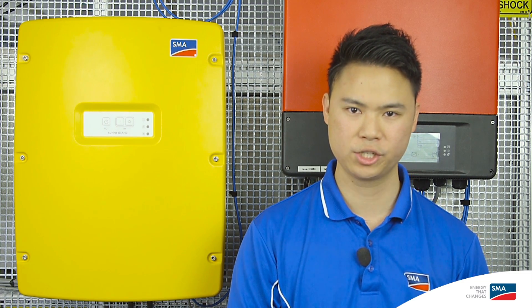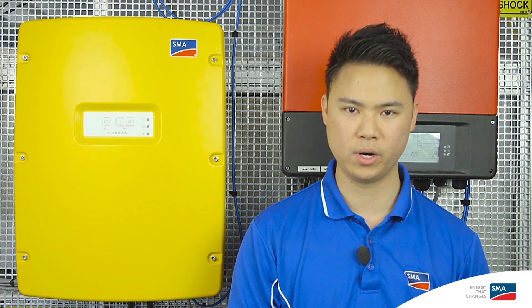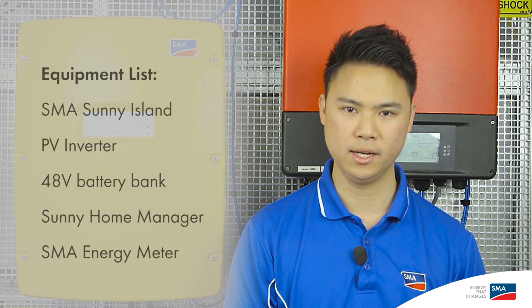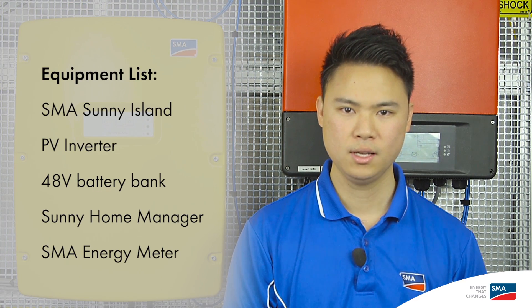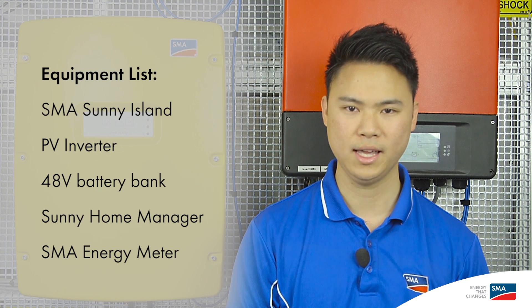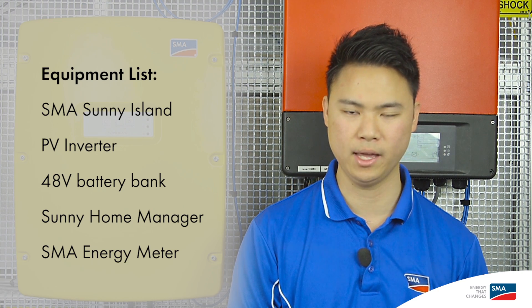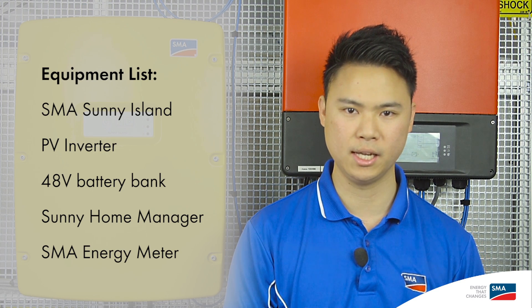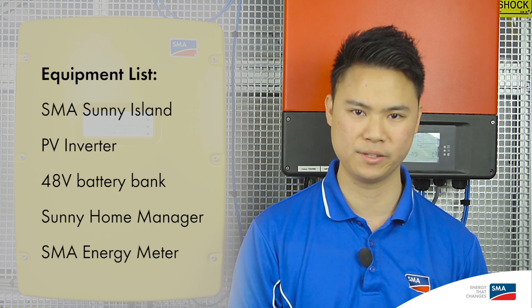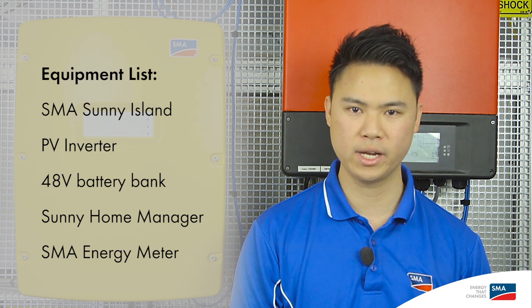Before we turn on the Sunny Island and configure the SMA Flexible Storage, let's review what equipment is required in the system. You will need an SMA Sunny Island, your choice of SMA PV inverters, a 48V battery bank, a Sunny Home Manager, and an SMA Energy Meter. Note that all SMA PV inverters and Sunny Island must comply with AS4777.3 to follow local regulations for grid connection and disconnection.